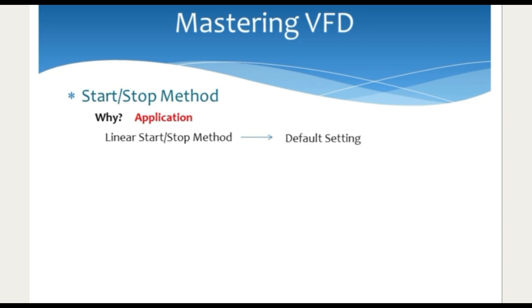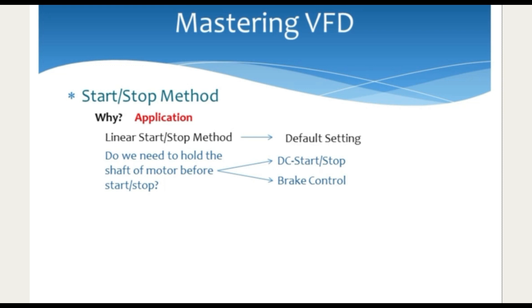If linear start is okay, then that's the default setting, which means the motor will ramp up and down linearly — as we have been viewing in all previous videos. Or, if we need to hold the motor shaft at start or stop, then we can select DC start or stop, or brake control.